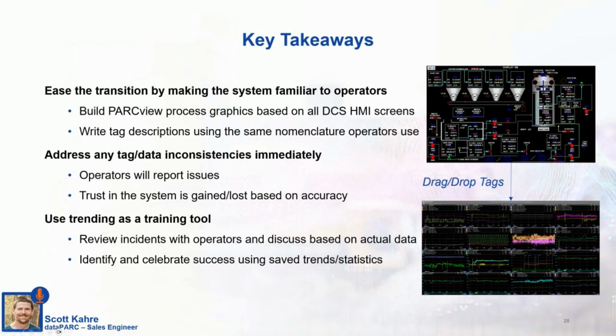What that did was it created a very familiar interface to the operators. So when they were ready to build trends, make changes to their own trends, or look at something ad hoc that they were trying to investigate besides what they always had on the screen, they could open these displays and their data parameters were in the same locations they were used to seeing on the DCS. All they had to do was double click one of those numbers and a trend would pop up, and then they could drag and drop more onto it from that display.